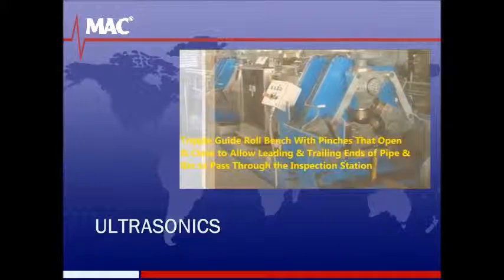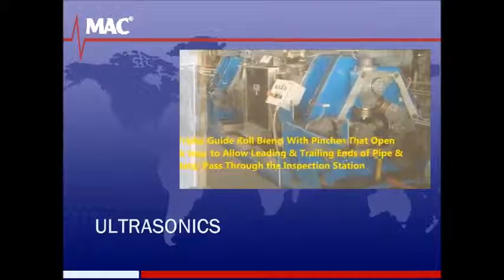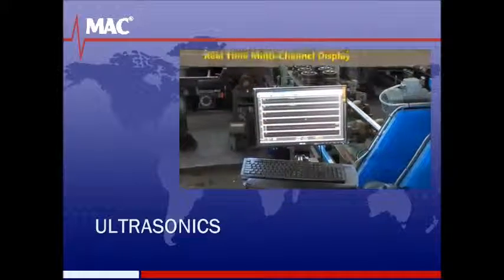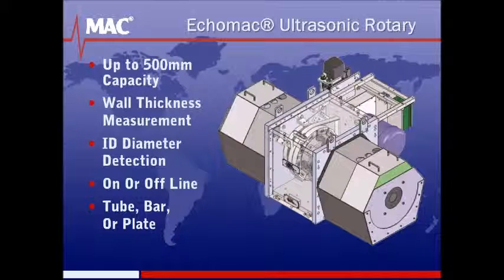MAC offers user-friendly electronics and a wide range of ultrasonic rotaries. The EchoMac rotary ultrasonic system includes rotating ultrasonic transducers that are available for shear wave configuration, detecting surface and subsurface defects, and compression wave configuration, detecting internal defects and dimensional measurements, such as wall thickness. Models are available for inspecting material from 5 to 500 millimeters in diameter, at test speeds up to 200 feet per minute, depending on the size and condition of the material.